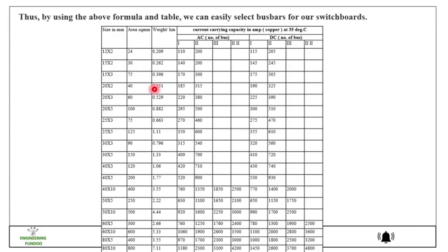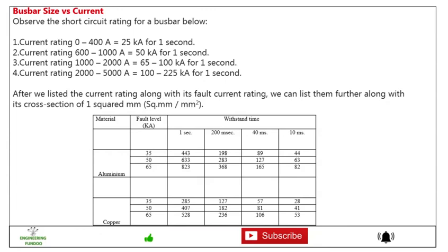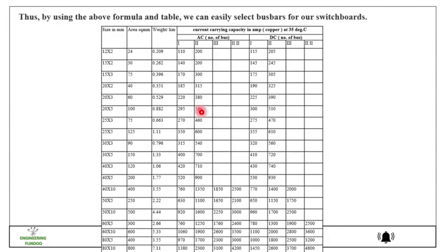And by using the above formula and table we can also easily select the busbar for our switchboard. Let's say you required, if we go back here you can see, let's say 89 square mm we need. So here for 89 square mm we can select this 90 mm area. This is 30 mm by 3 mm cross section size.